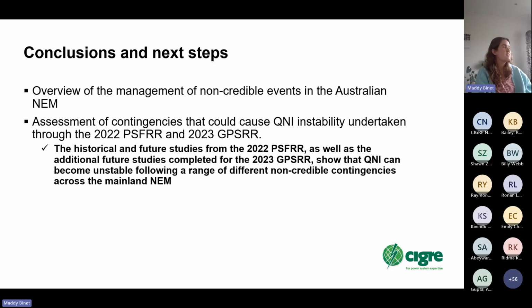In terms of improving analysis of non-credible events, I think the incident investigations are really good in terms of tying that into the risk review and making recommendations based on actual events that have happened. But I think the key thing is having accurate power system models, accurate information from generators, and accurate protection settings, because a lot of unexpected cascading failures end up being due to unexpected protection operations or settings we didn't know were there, or settings that were wrong.